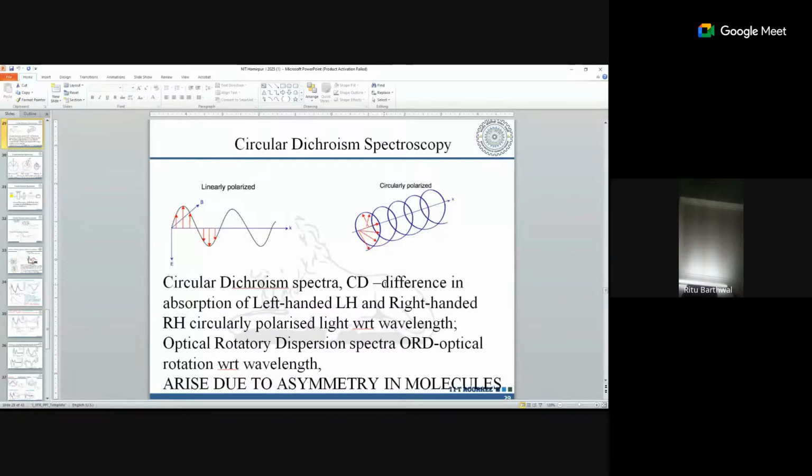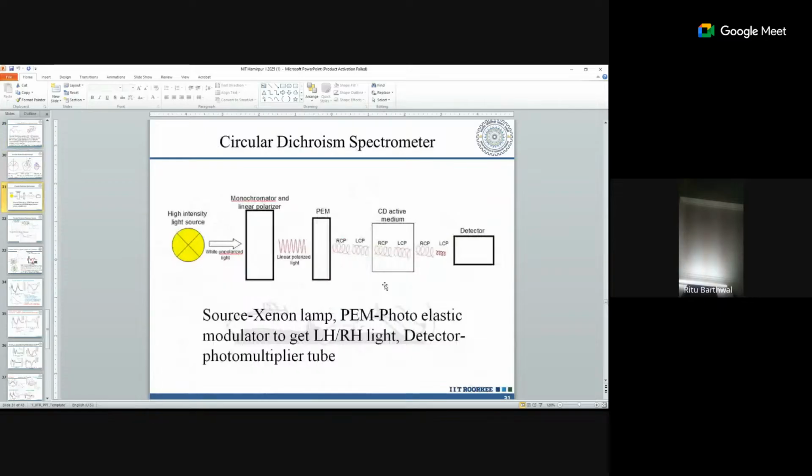What sources of light? Xenon is normally used in some instruments. Earlier we were using a tungsten lamp. They all emit unpolarized light. When we let it pass through a device which we call a polarizer, a particular kind of crystal, it will absorb light with electric fields in all sorts of directions except one particular selected one. This selection is according to how we orient the crystal. So we use normal lamps, a xenon lamp, then we place a polarizer in front of that, and what we get is linearly polarized light.